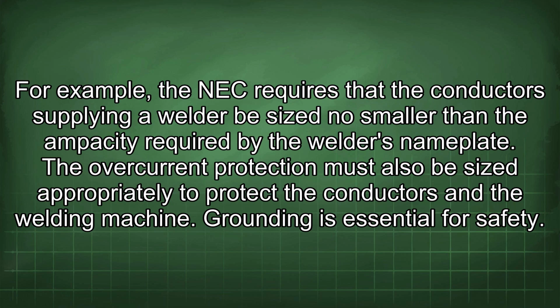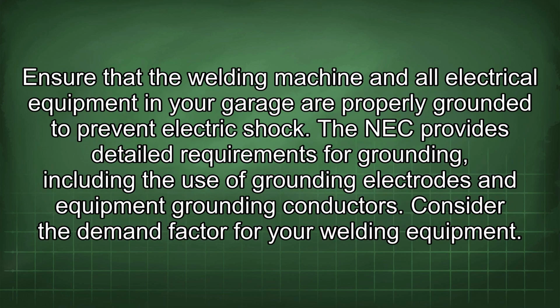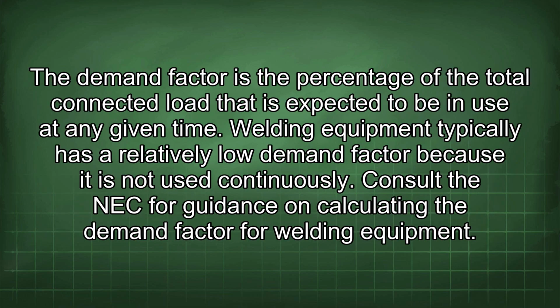Grounding is essential for safety. Ensure that the welding machine and all electrical equipment in your garage are properly grounded to prevent electric shock. The NEC provides detailed requirements for grounding, including the use of grounding electrodes and equipment grounding conductors. Consider the demand factor for your welding equipment. The demand factor is the percentage of the total connected load that is expected to be in use at any given time. Welding equipment typically has a relatively low demand factor because it is not used continuously. Consult the NEC for guidance on calculating the demand factor for welding equipment.